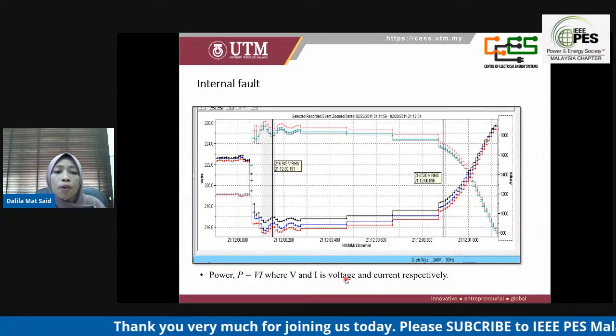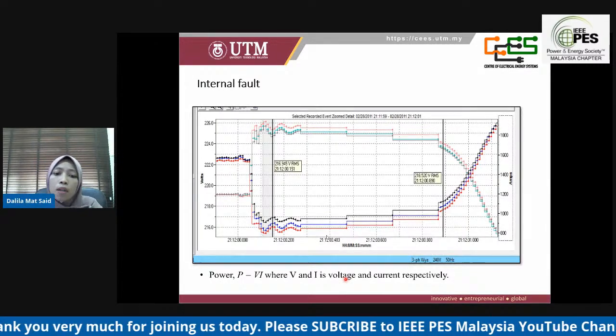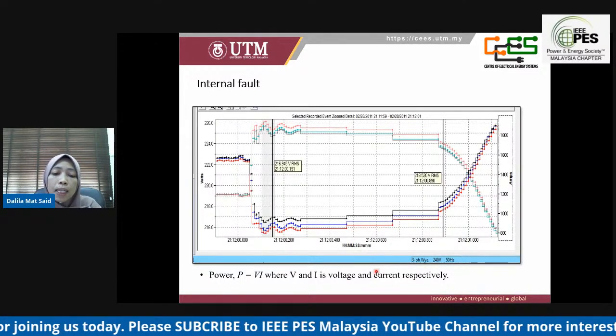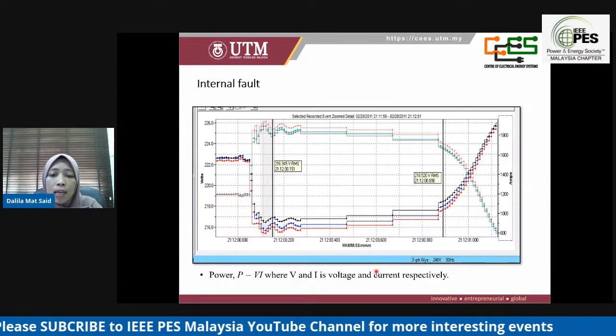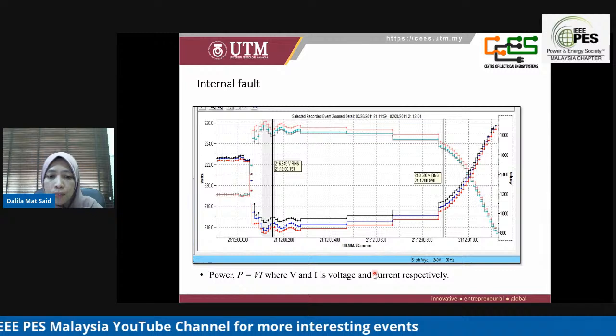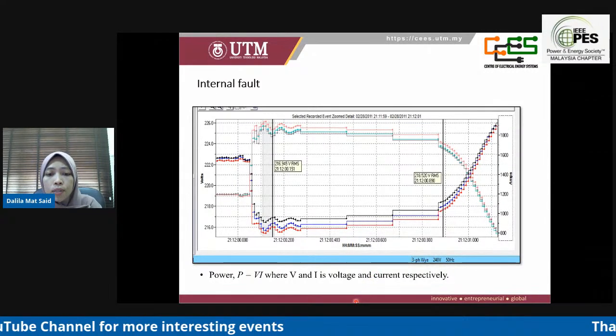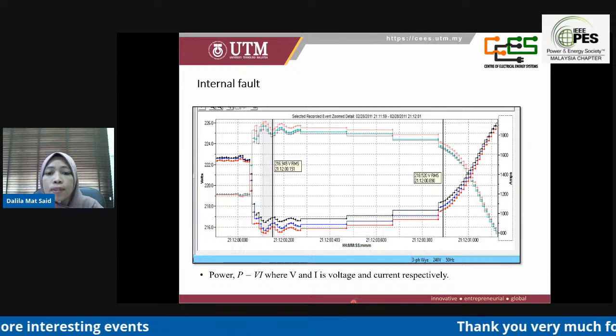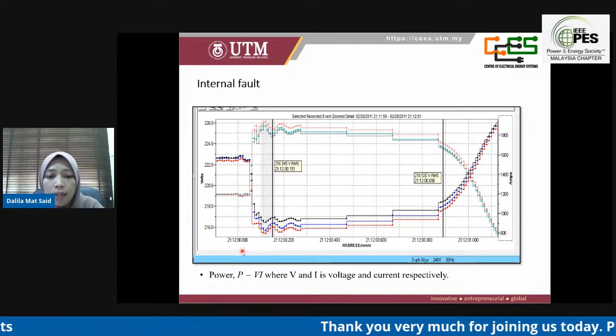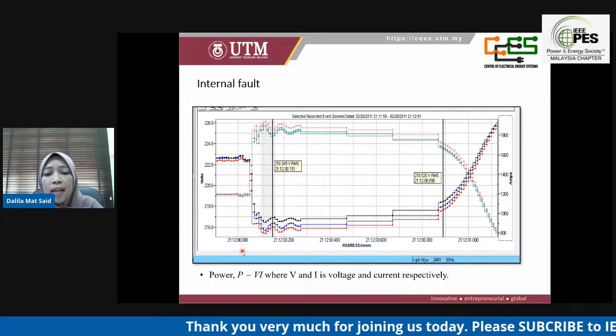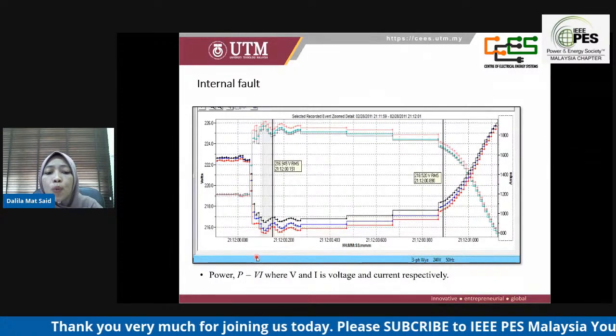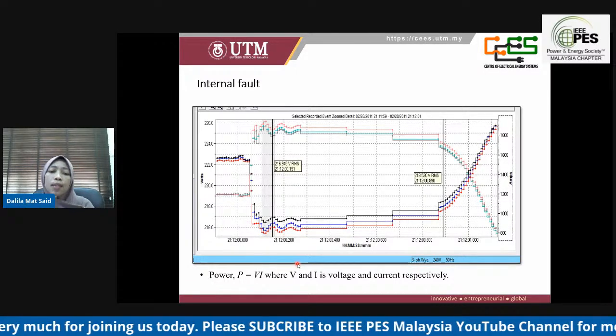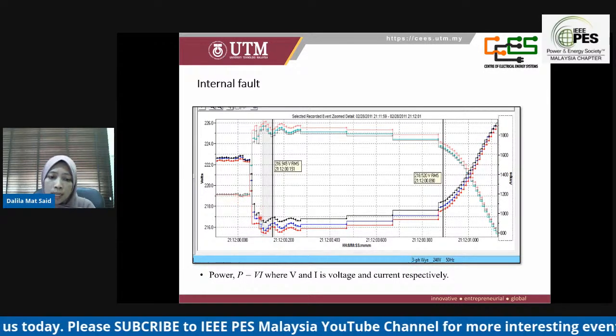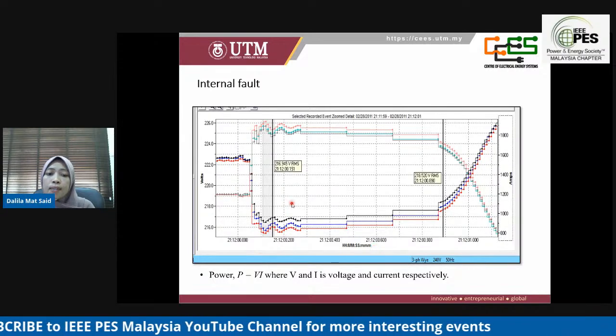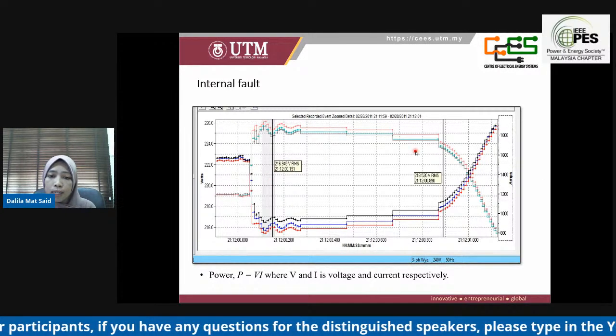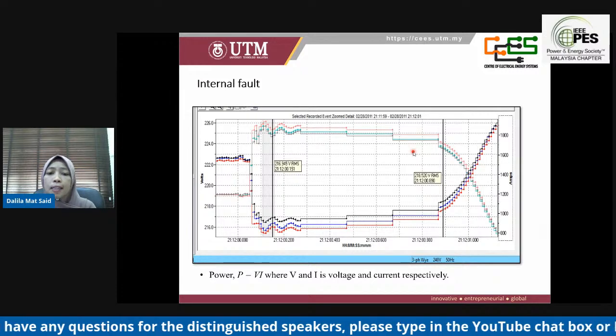And for an internal fault, from the concept of power, P equals VI, where V and I are the voltage and current respectively. During the startup of a large load or motor, the incoming power is considered constant. The current will increase as it has to supply the large load, which will make the voltage tend to decrease. This means that when the voltage decreases and you see the current increase, we can suspect it is due to an internal fault.